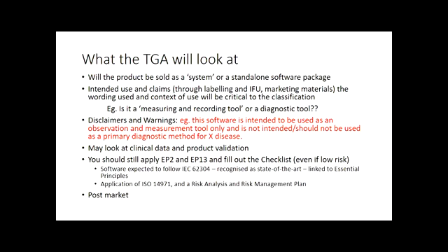They might look at your clinical data and product validation, even if it's a lower class device, and you should still apply Essential Principle 2 and Essential Principle 13 and fill out the checklist, even if it is low risk. Again, use this standard. It is recognized as state of the art, and it is directly linked to the essential principles.